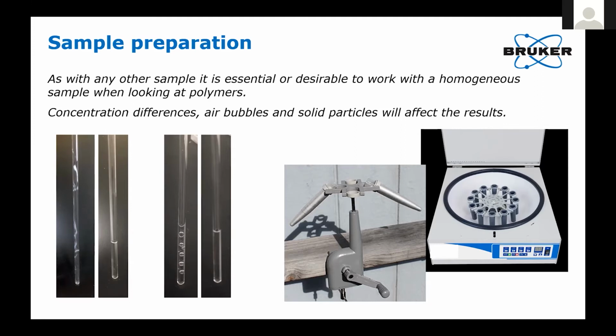But if you have something medium viscous and you try to get it all to the bottom or get it bubble free, centrifuges are really helpful. And the hand crank centrifuge is a wonderful tool for almost any NMR spectroscopist, because you can effectively spin the viscous material to the bottom of the tube, or you can spin the solution to the bottom of the tube, and the air bubbles, being lighter, go up. Or if you have a fancy centrifuge like the one on the right, you can tape the tubes down to the hub in the middle, close the lid and spin it for maybe 30 seconds to a minute at less than 1,000 RPM, and it'll be fine.